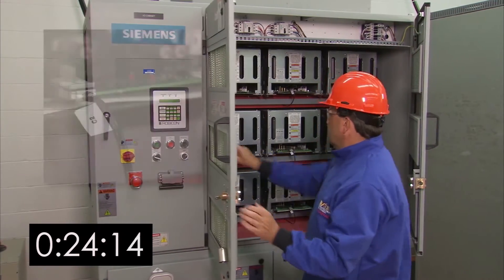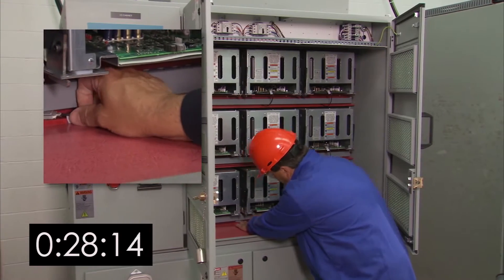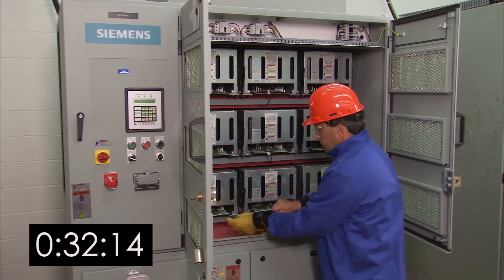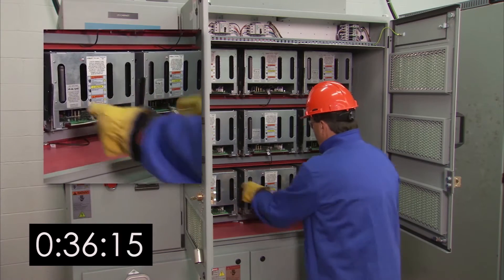Verify that all the pre-charged lights are off, and then remove the fiber optic link connection. Secure it in a location where it will not be in the way when you're pulling out the cell assembly.